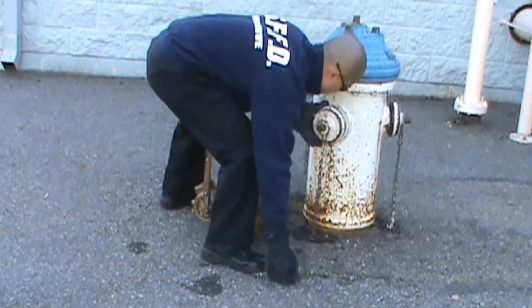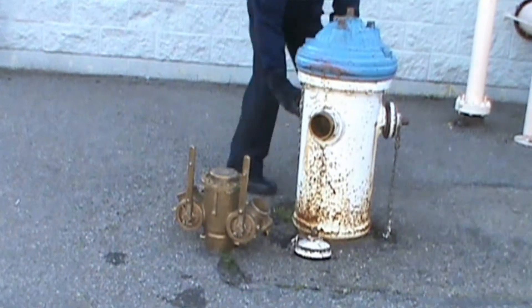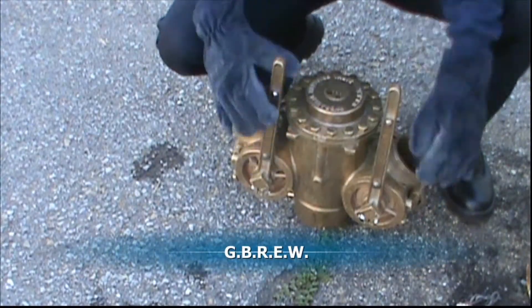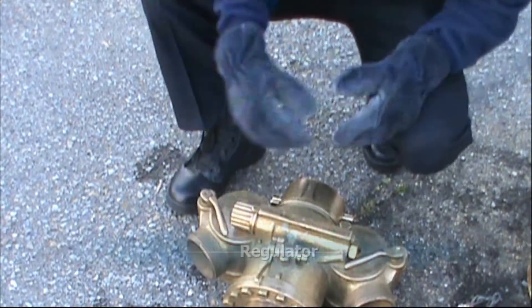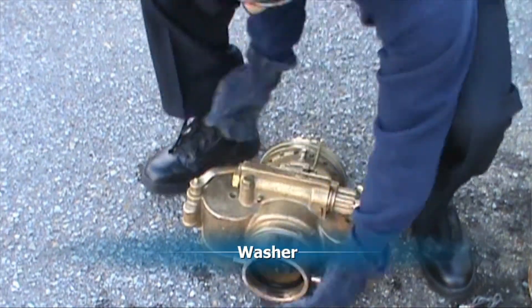In preparation to install a Gleason valve, remove all the hydrant caps and inspect to ensure gates are centered. Next, use the acronym GBREW to ensure gates are closed, bleeders are closed, regulator is set to zero, emergency shutoff is down, and the washer is present.